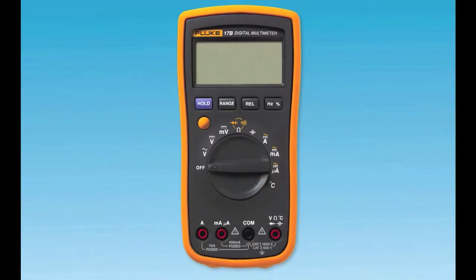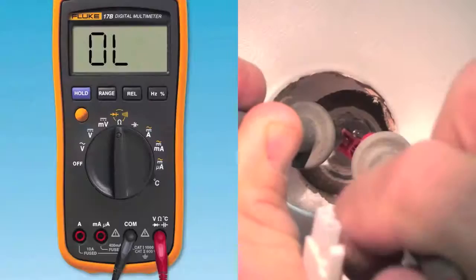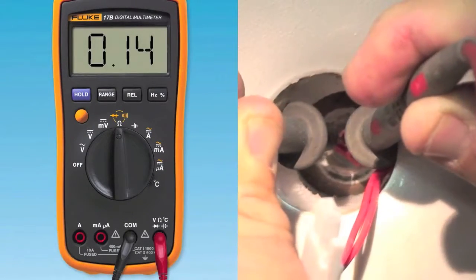To check the high-limit safety switch, set your meter to ohms and place the leads of the meter into the connector. You should measure resistance, which means that the switch is in the closed position.